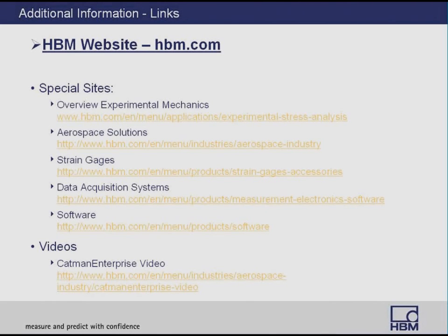All right. Another person is asking, when do you recommend the TID versus TEDS? Well, the TEDS is usually used for all types of transducers, for example, that have calibration scaling information, or even maybe a polynomial curve defined. There you can use the TEDS, and then the amplifier would set itself up automatically. The TID is, I would say, nearly 100% used with quarter bridge strain gauges.